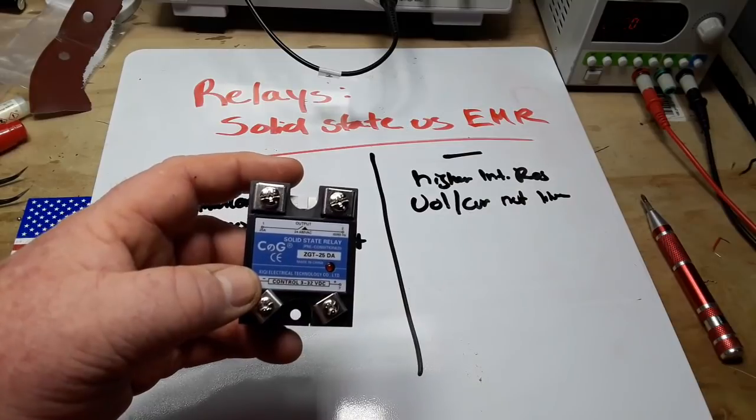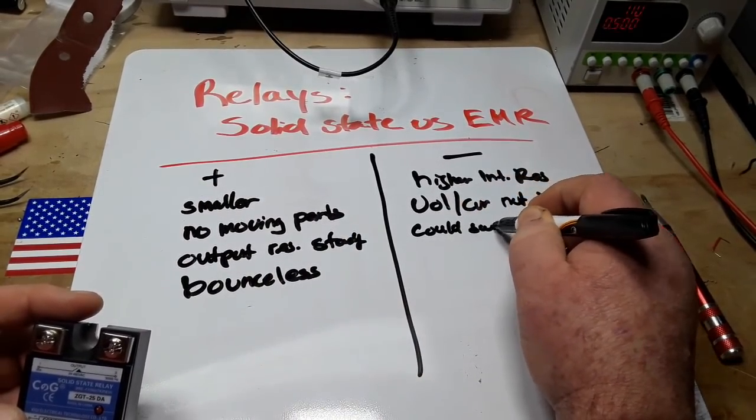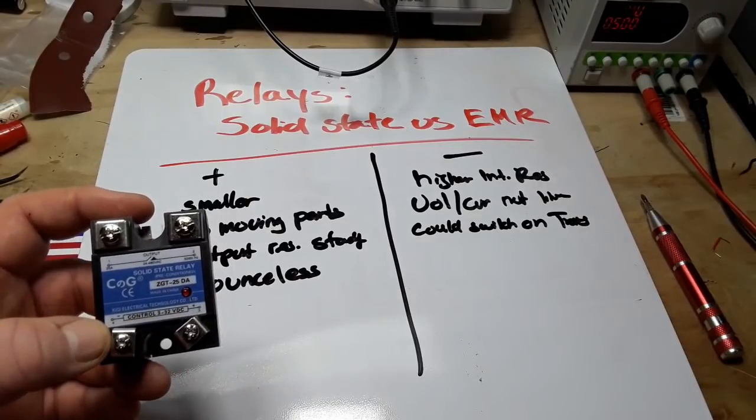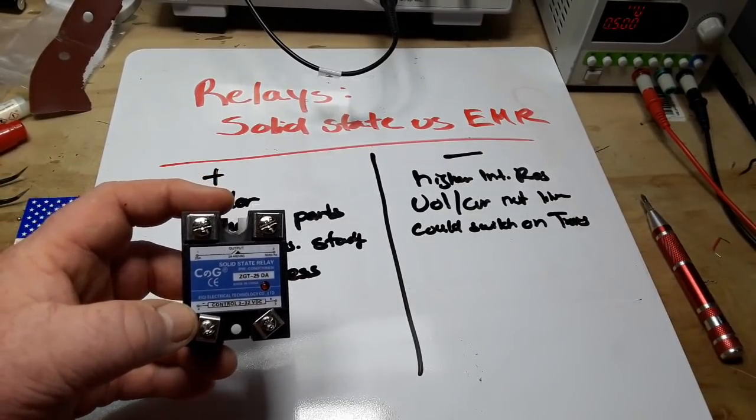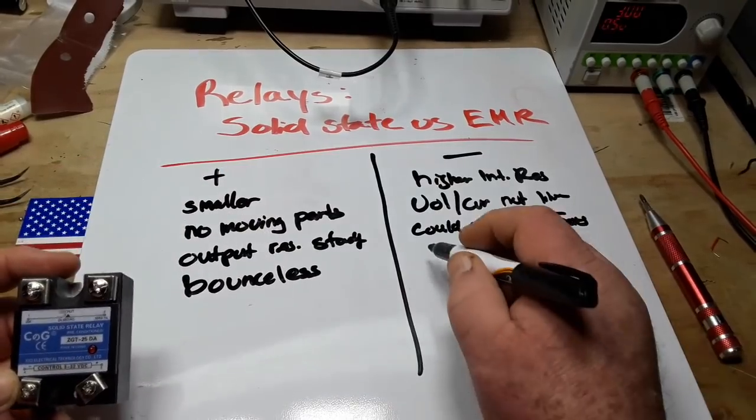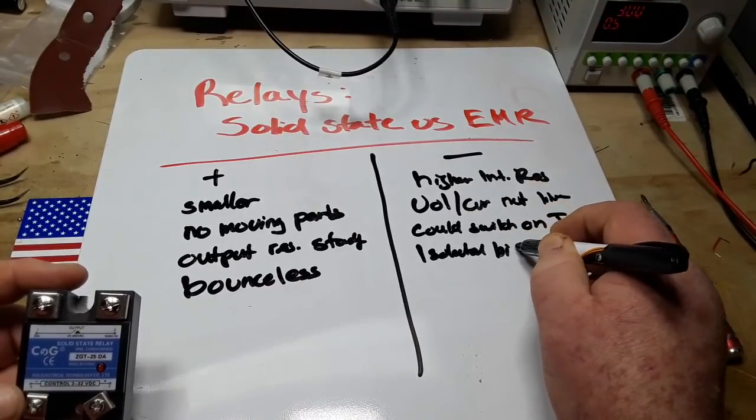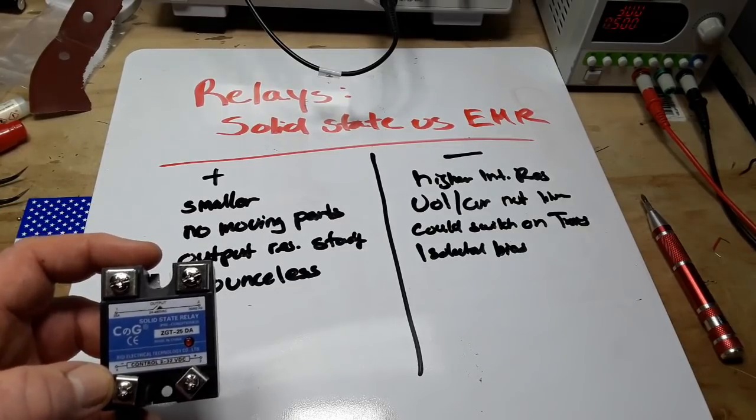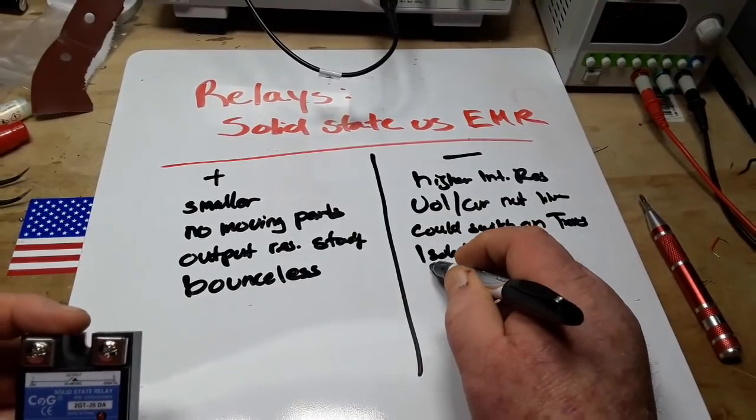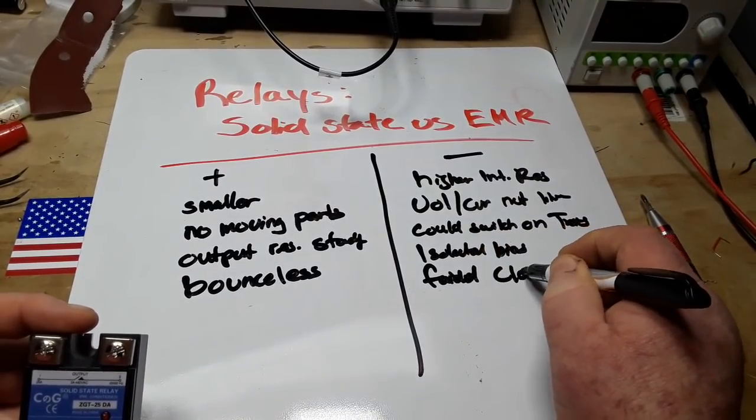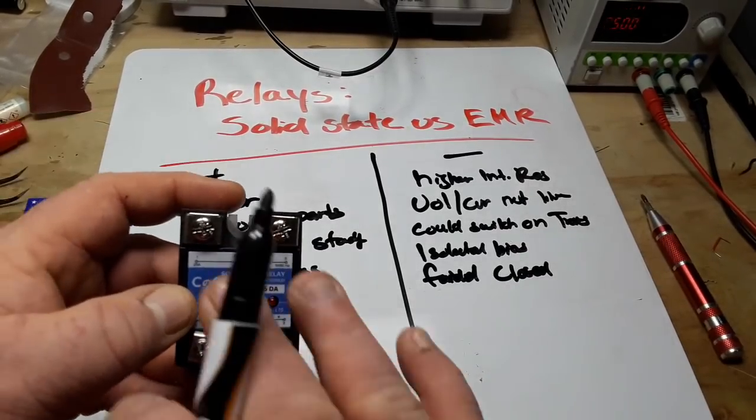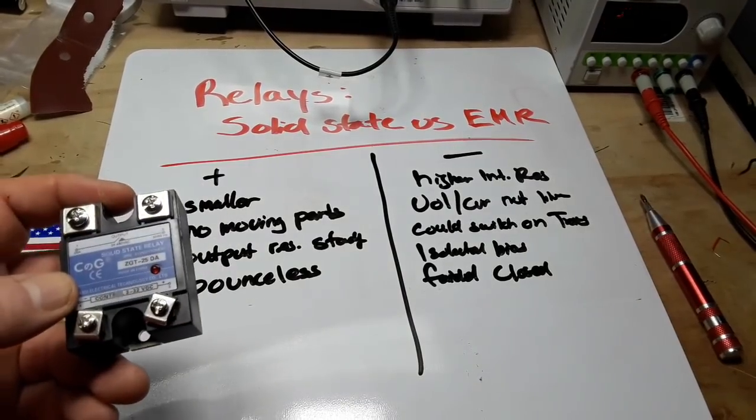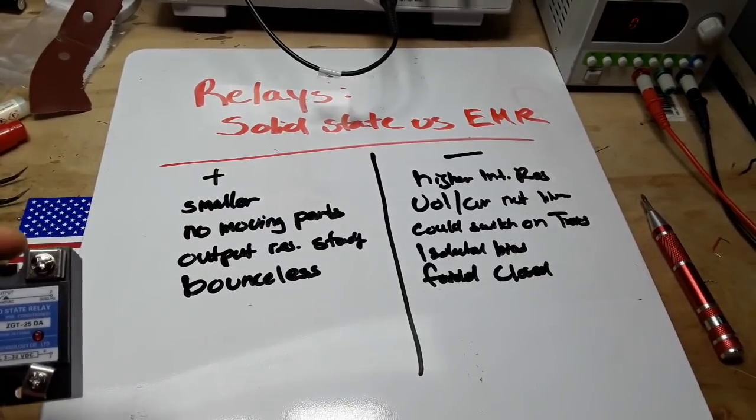There is a possibility that they could switch on transients. So if there was a strong spike somewhere else in the circuit, it could set this off. They also require an isolated bias supply. Not really a big deal, but you don't necessarily need that on an electromechanical relay. And what I find to be the biggest fault is they fail closed. So if they fail, they generally fail with the output on, as opposed to an electromechanical relay, which will generally fail with the output off. To me, that's a big thing, but whatever you need for your application.